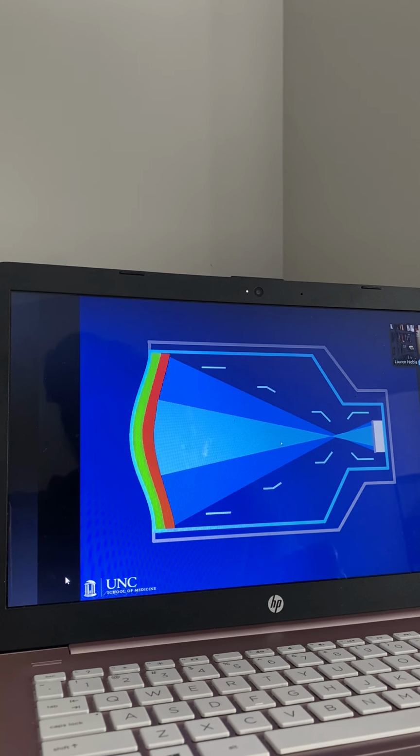Since the beam is narrow because of a smaller input area and because of the increased voltage to the lenses, we get a lot narrower beam than what we have with the 30 centimeter input phosphor. So that focal spot has shifted. See, it's shifted further back. It's a little further away from the output phosphor.